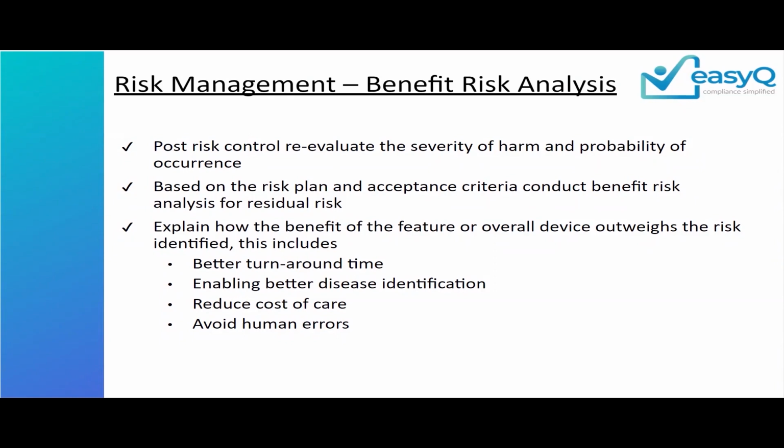Very, very important, guys. Please put some time and thought when you are defining your benefit risk analysis. Do not use blanket statements, right? For different features, you need to talk about different benefit risk analysis. And if it is at product level, then you can definitely talk about your overall product's benefit risk analysis. Give references to the articles if you have any publications, if you might be aware of any, that will also strengthen your overall benefit risk analysis.